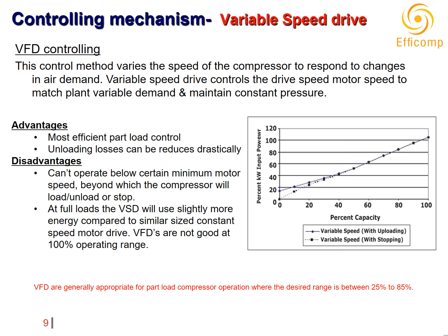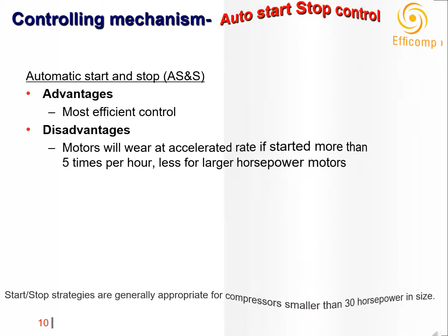This is the simplest and most efficient control strategy. It can be applied to either reciprocating or rotary screw compressors. Essentially, the motor driving the compressor is turned on or off in response to the discharge pressure of the machine. For this strategy, a pressure switch provides the motor start-stop signal. Start-stop strategies are generally appropriate for compressors smaller than 30 horsepower in size. Repeated starts may cause the motor to overheat and place greater maintenance demands on compressor components. For this reason, care should be taken in sizing storage receivers and maintaining wide working pressure bands to keep motor starts within allowable limits. The table shows the different ranges and pressure bands to be considered before selecting any compressor.